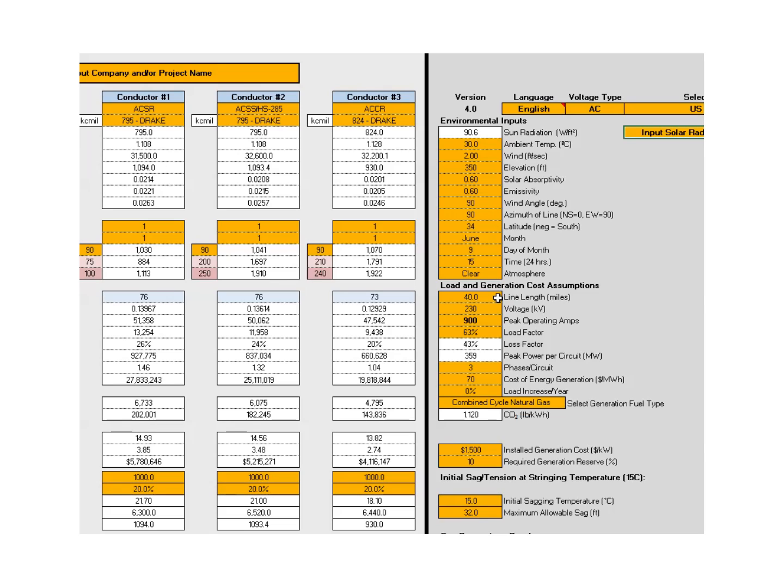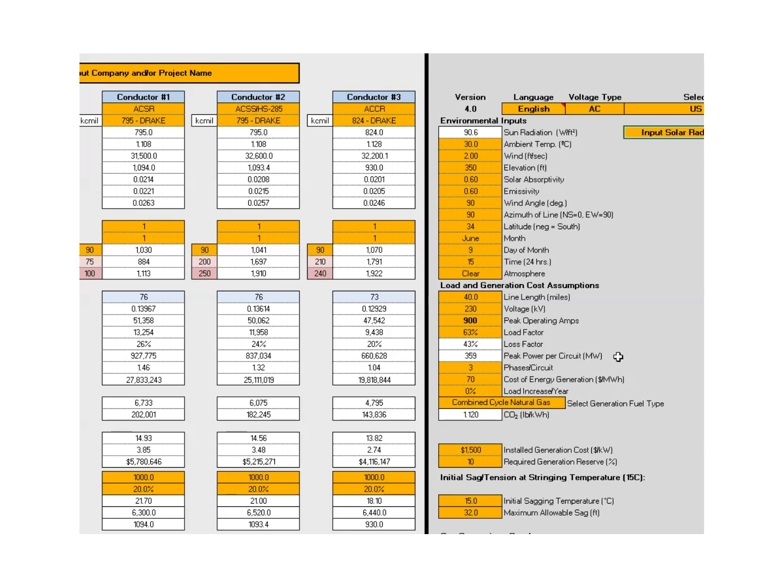For comparison, we're going to use 40 miles for this comparison. The voltage is 230 kV. The existing peak ampacity is at 900 amps. Load factor, which is about standard for California, is 63%. It calculates loss factor. And the peak circuit megawatts is about 359. Again, this is AC with three phases, single circuit. Here we've made an assumption that the cost of generation is $70 per megawatt hour or 7 cents per kilowatt hour.